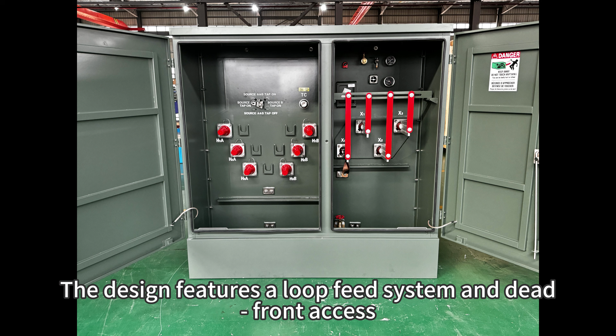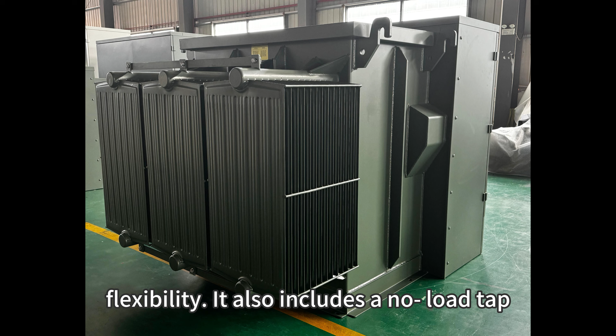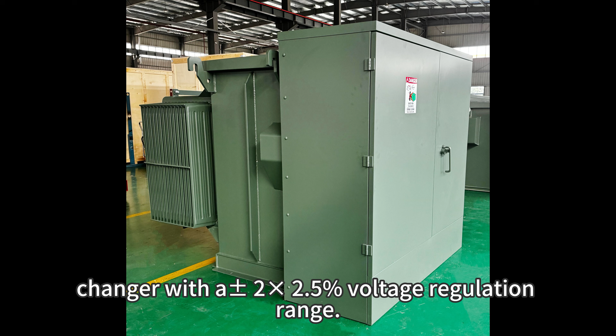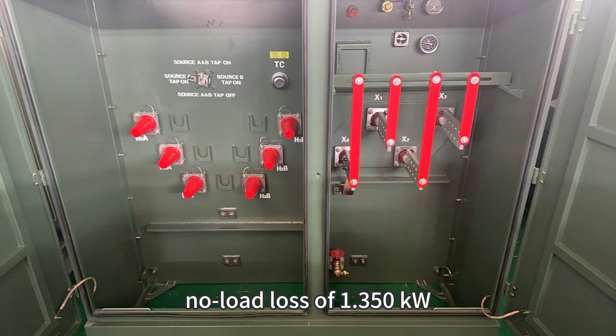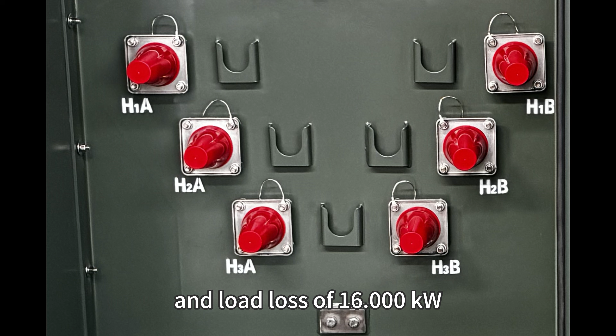The design features a loop feed system and deadfront access, supporting both safe operation and installation flexibility. It also includes a no-load tap changer with a plus/minus 2 times 2.5% voltage regulation range, with an impedance of 5.75%, no-load loss of 1.35 kW, and load loss of 16.0 kW.